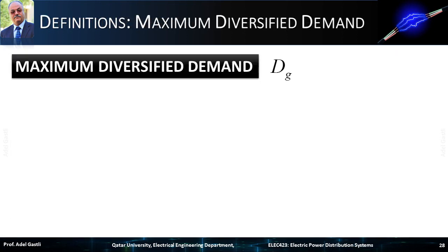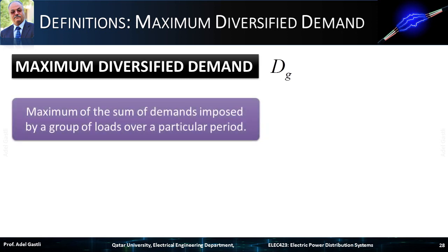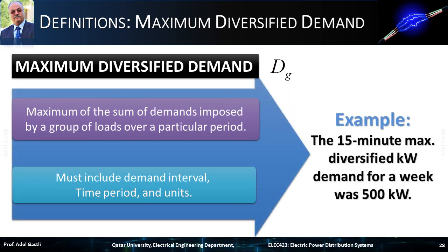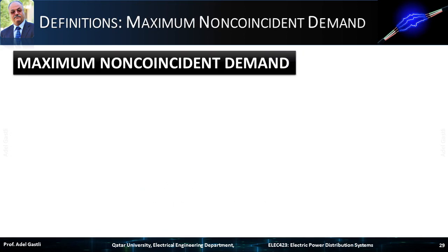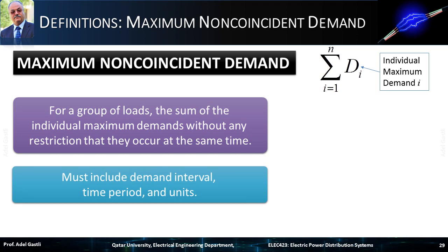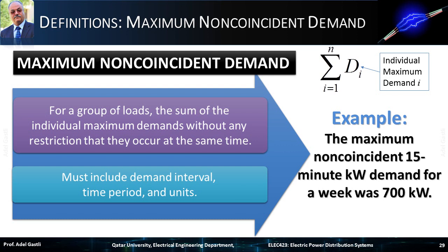Next, we will define the maximum diversified demand. It is the maximum of the sum of demands imposed by a group of loads over a particular time period. It must include demand interval, time period, and units. For example, the 15-minute maximum diversified kilowatt demand for a week was 500 kilowatts. Next, we will define the maximum non-coincident demand. It is defined for a group of loads as the sum of the individual maximum demands without any restriction that they occur at the same time. For example, the maximum non-coincident 15-minute kilowatt demand for a week was 700 kilowatts.